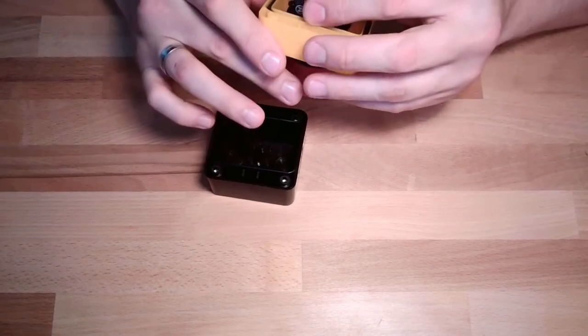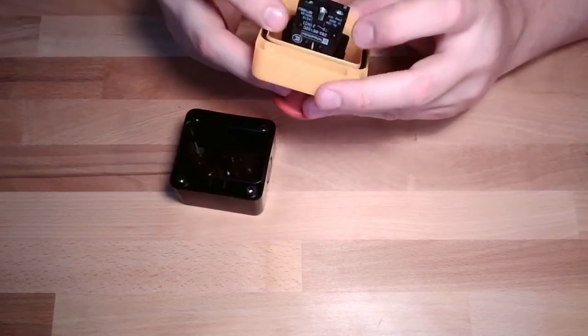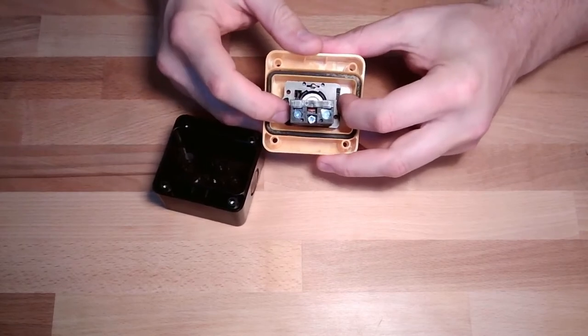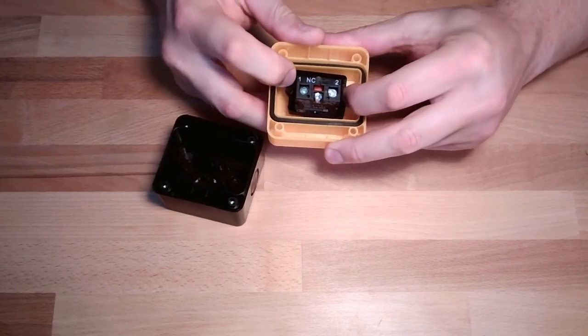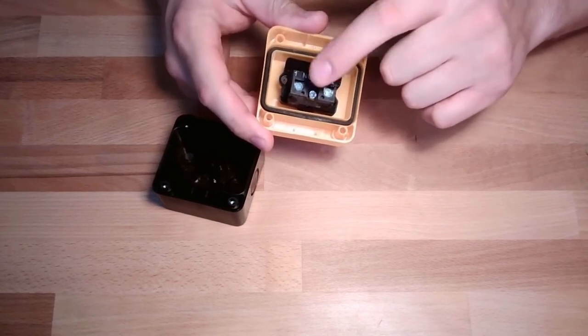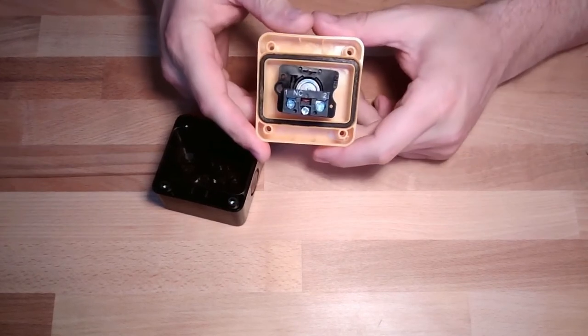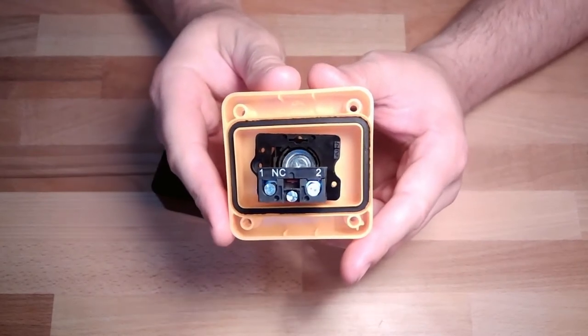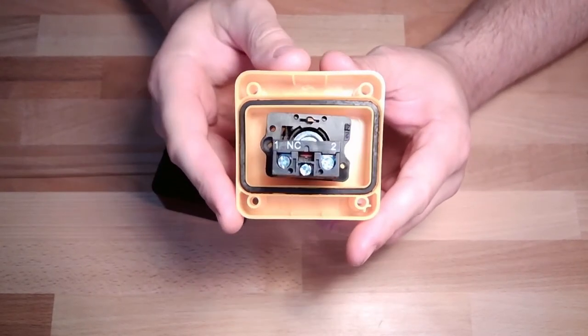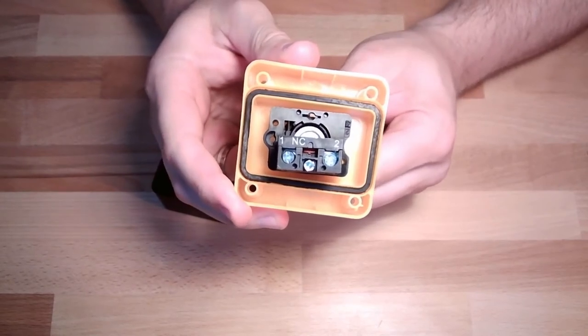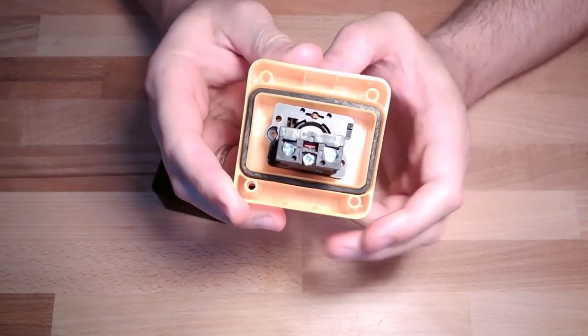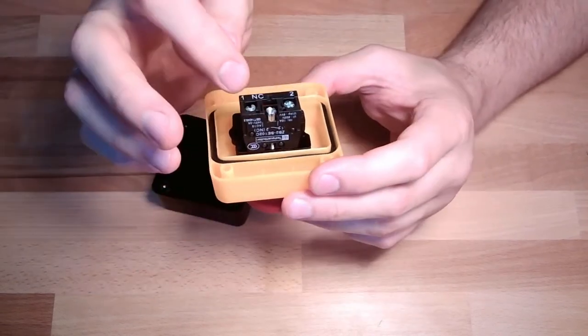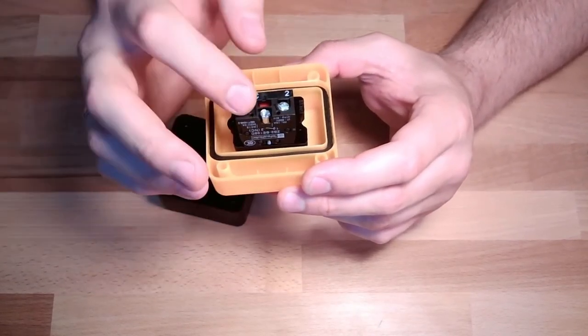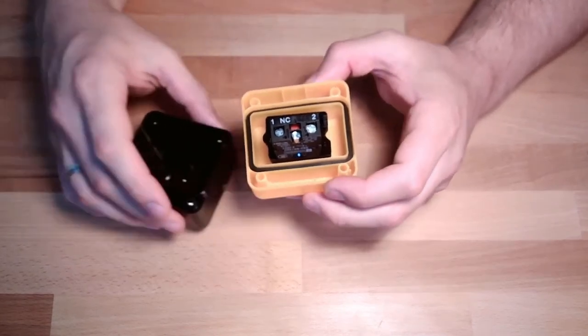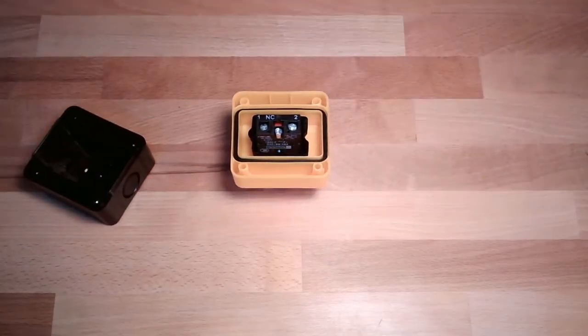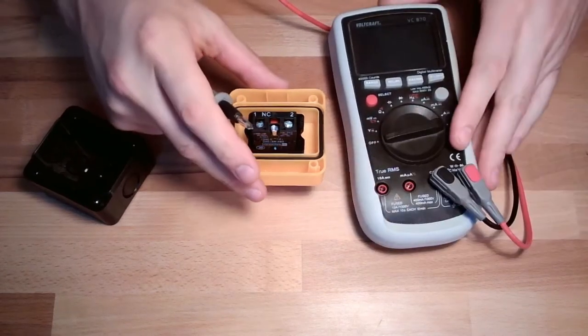Inside, we see it's not really a fully equipped emergency push button, because an emergency push button usually has two contacts. But what we can see, look at this, here's written NC. This means normally closed. So if it's not operated right now, then this connection is given. If it's operated, this connection is open. I am going to check this with my multimeter here.